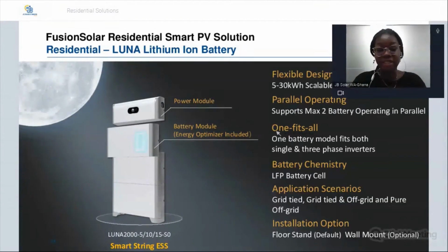The batteries have a flexible design in that you can have from 5 kilowatt hours all the way to 30 kilowatt hours, and it's scalable. The maximum you can have is 30 kilowatt hours, which is 2 racks. Each rack - this is 5, this is 5, this is 5 - with the power module together is 15 kilowatt hours. You can have just this, and later on if you want another one, you can add one more, then add another one.